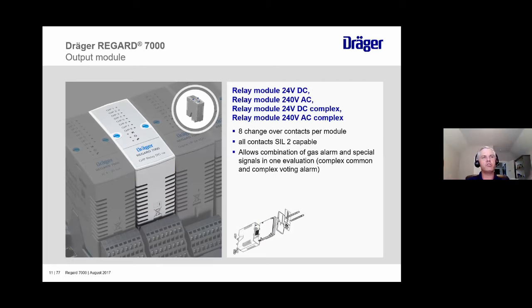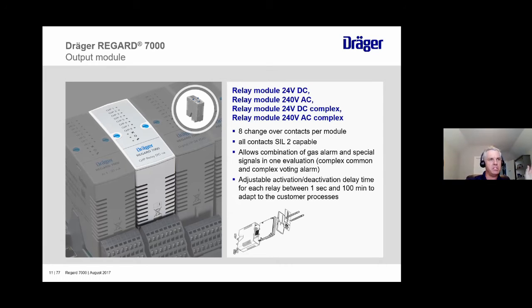Well, guess what? On traditional controllers, because all 4 points aren't actually in alarm, you're not turning on that big mitigation activity or whatever you decided to do if all 4 points go into alarm. That's when you use the complex relay modules, because you can set it up so that if that point goes into fault or alarm, you can trip the alarm at that point. So that's some of the extra reliability that we've built into the REGARD 7000 through some of these modules. And we also have an adjustable activation delay time from 1 second to 100 minutes for those alarms.